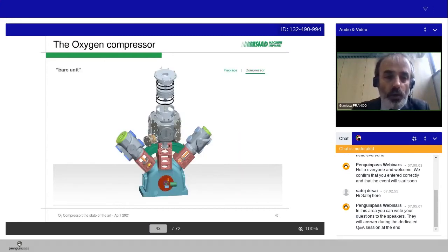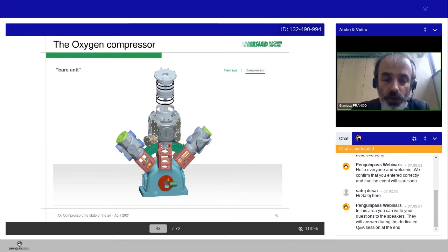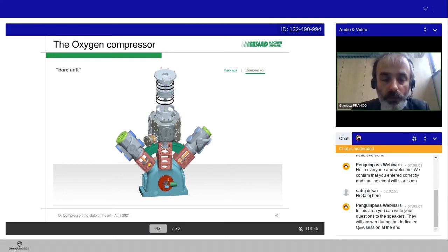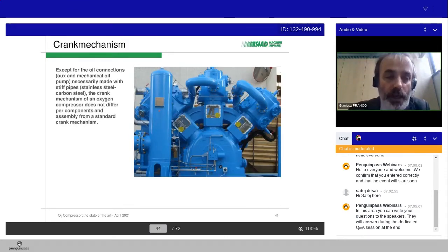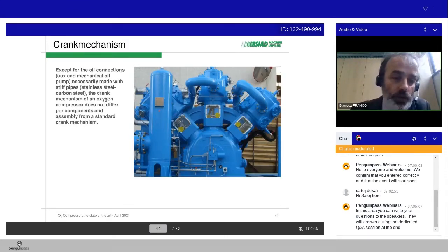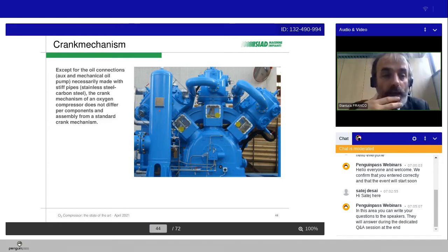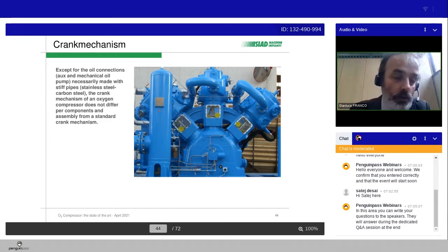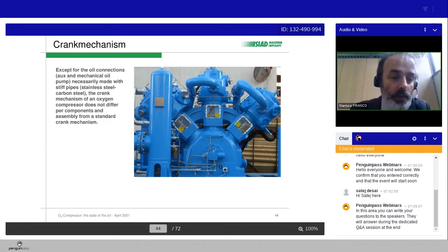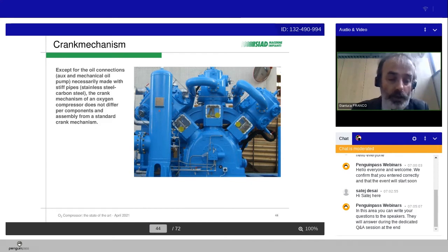Let's give a look now to the bare unit, which are our design criteria for the bare compressor, for safety and for the best performances according to customer needs. About the crank mechanism, except for the oil connection, the auxiliary and the mechanical oil pump, necessarily made with stiff pipes, for example, carbon steel or stainless steel, the crank mechanism of an oxygen machine does not differ per components and assembly from a standard crank mechanism.